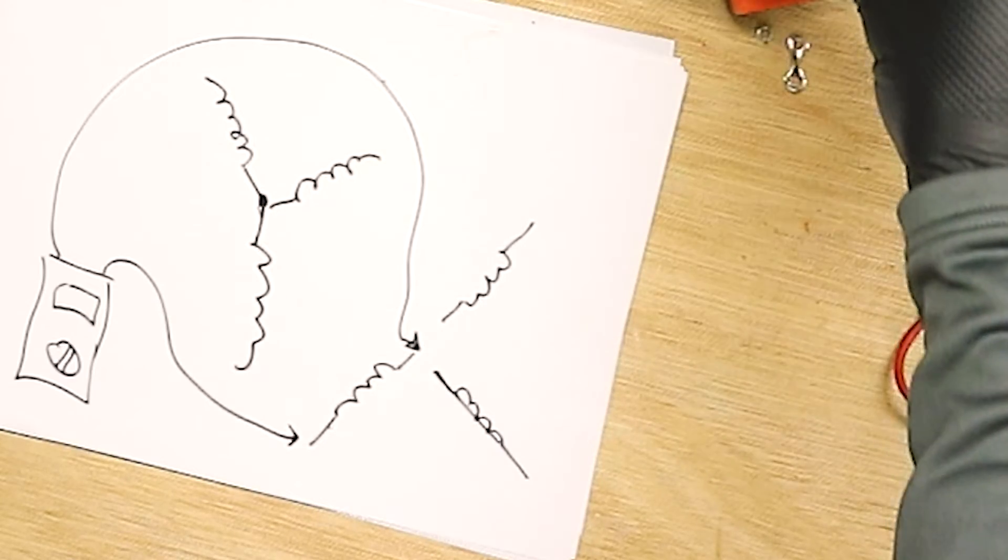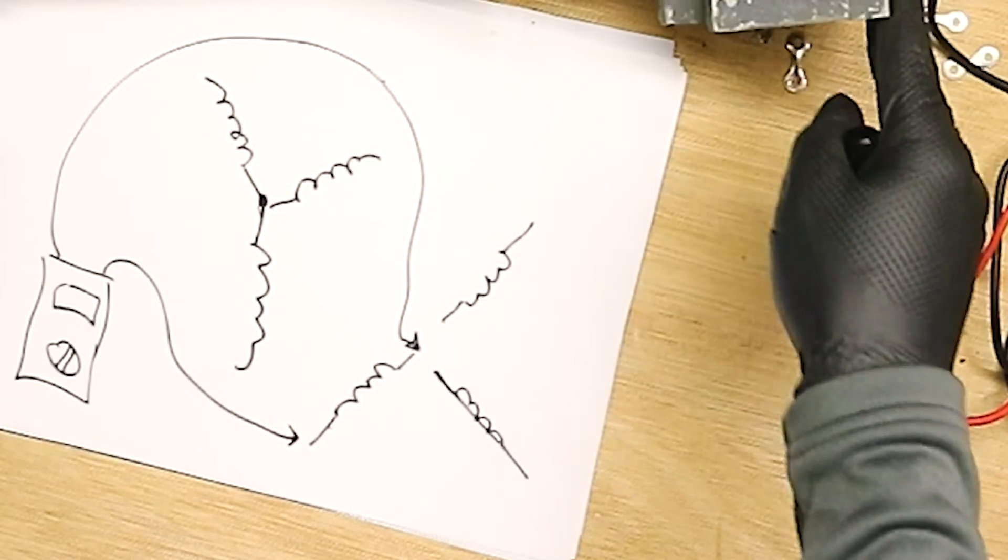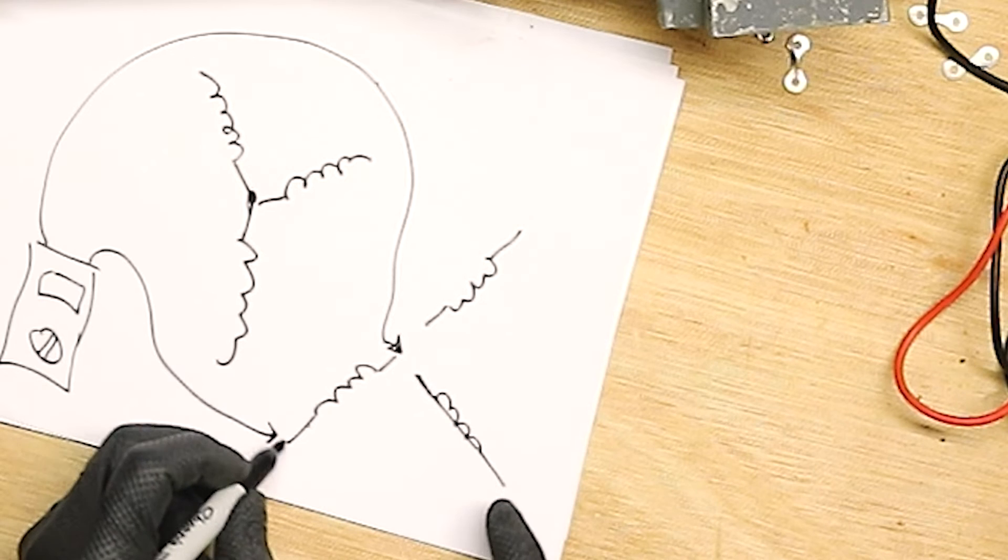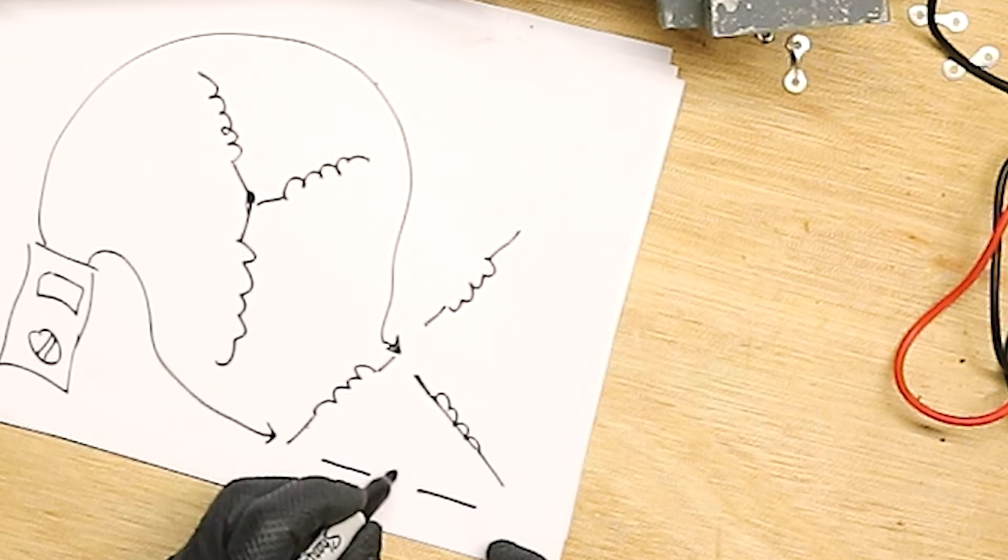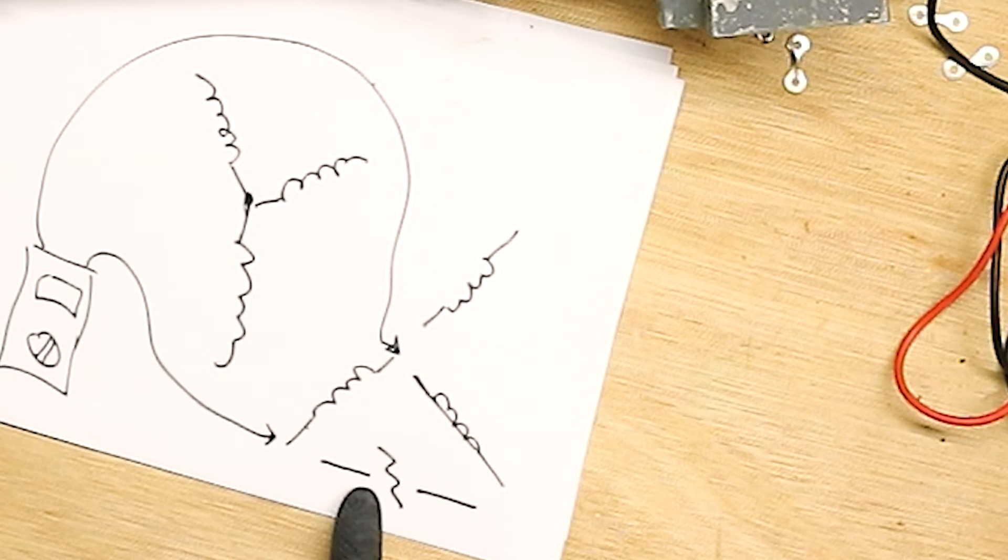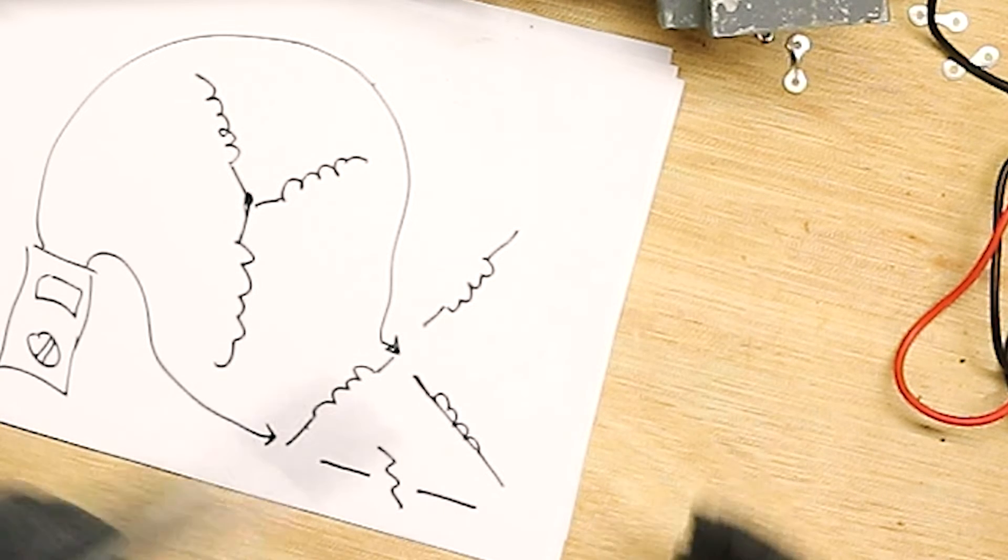So basically, it means that our winding has a break in it somewhere. There is a break in the middle of it. I don't know what that symbol is, but that's signifying that there's a break in the winding. And it's across all three.